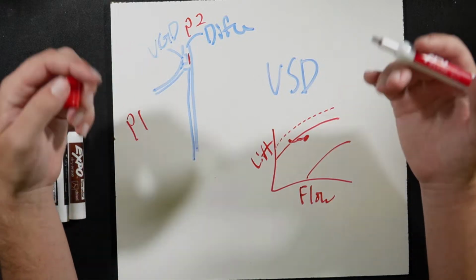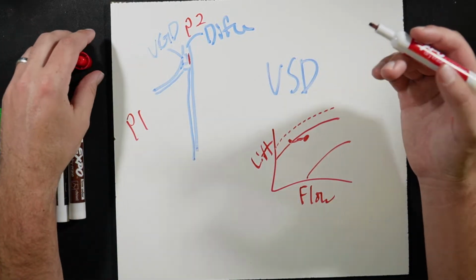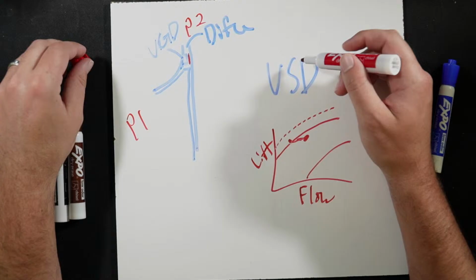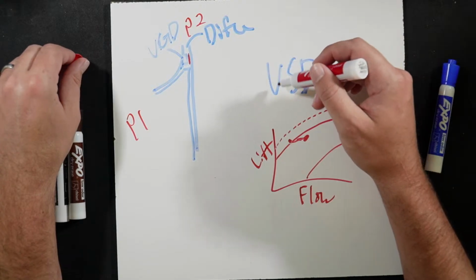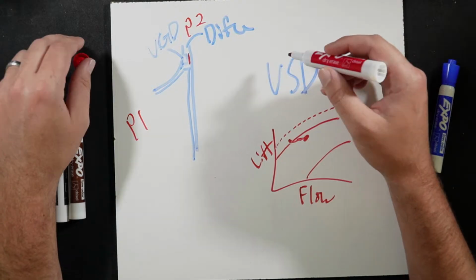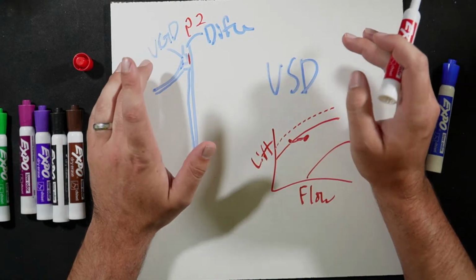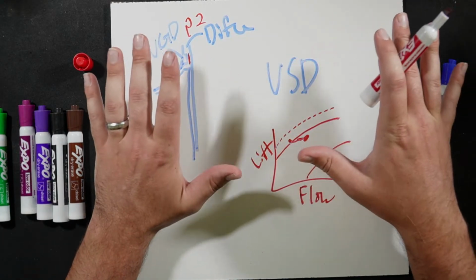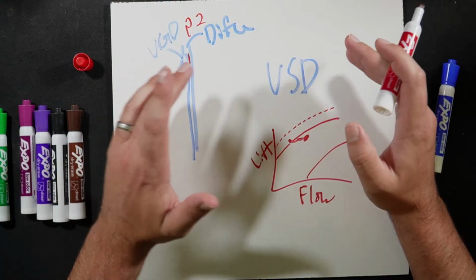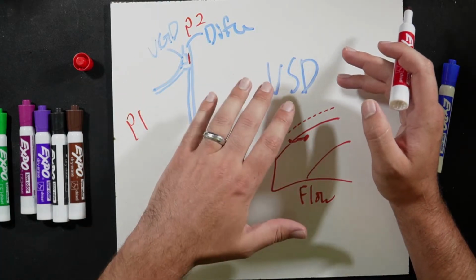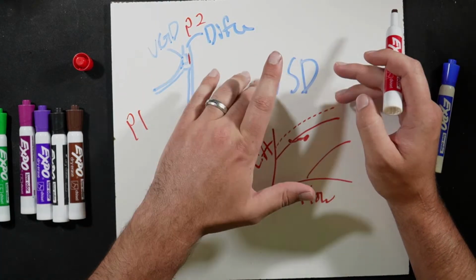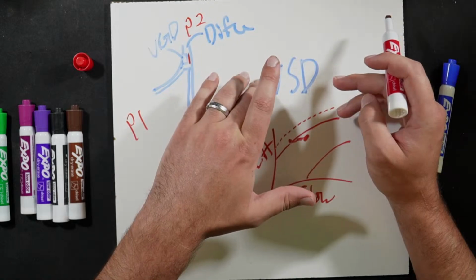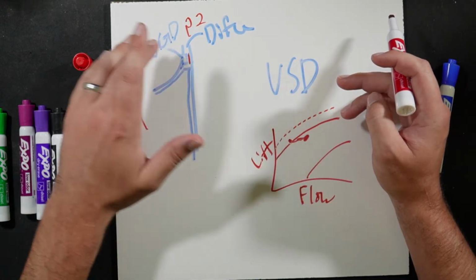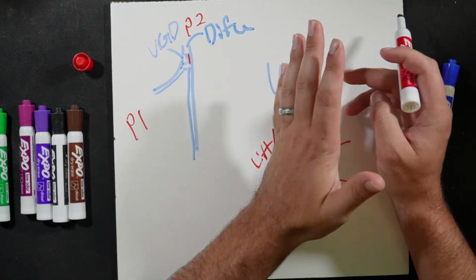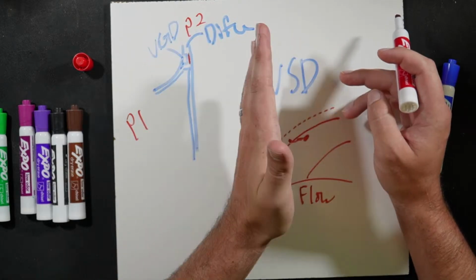If I'm going to approach this from, say, a York perspective, then the VSD is going to be the primary, or let me take a step back actually. From startup, your chiller will come online with your VSD at minimum speed first. Okay, so it's going to be at minimum hertz, and your VGD should be in a full closed state. It's pushed all the way out.